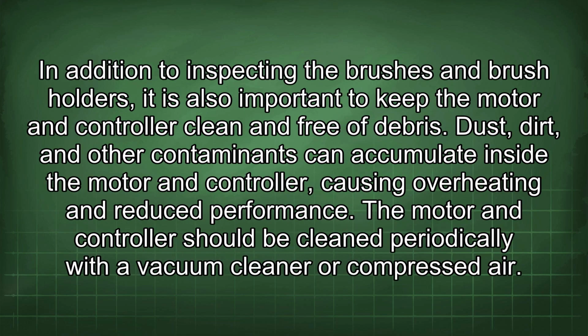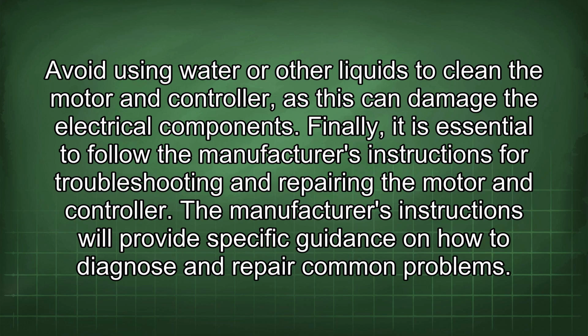In addition to inspecting the brushes and brush holders, it is also important to keep the motor and controller clean and free of debris. Dirt and other contaminants can accumulate inside the motor and controller, causing overheating and reduced performance. The motor and controller should be cleaned periodically with a vacuum cleaner or compressed air. Avoid using water or other liquids to clean the motor and controller, as this can damage the electrical components.